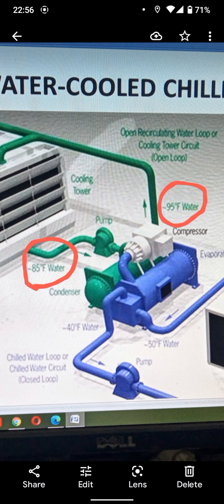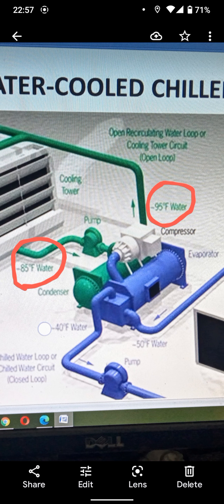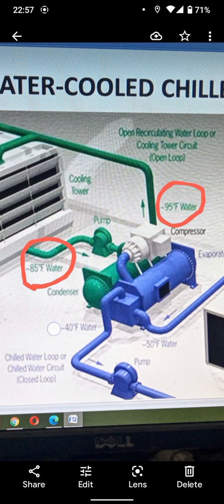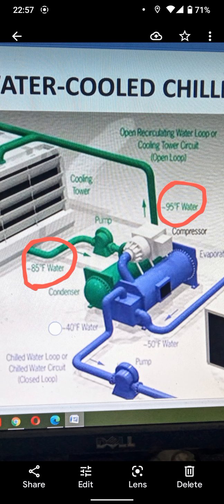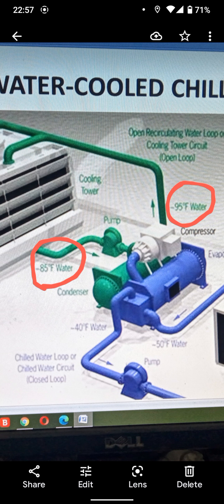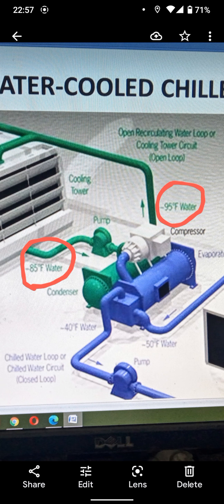My experience is with startup and commissioning. My company sent me to one site where they had installed four Evergreen centrifugal chillers, I think 1500 tons each, with variable diffuser valves, and five condenser water pumps, five chilled water pumps, and four cooling towers. They sent us to commission it. When we got to the site, they had installed everything, waiting for the commissioning team to come and start the chiller. We did our normal job: we checked the chiller, did the leak test, pressure test, and vacuum test, then charged the refrigerant and finally started the chiller.